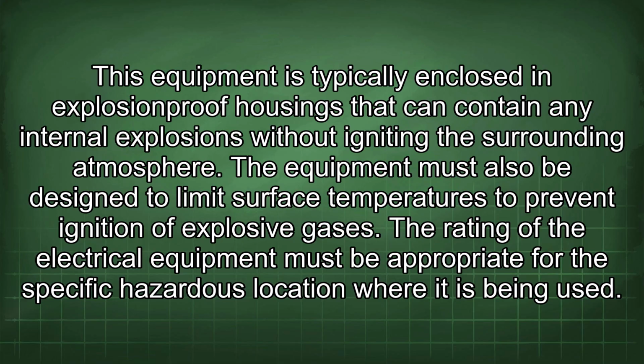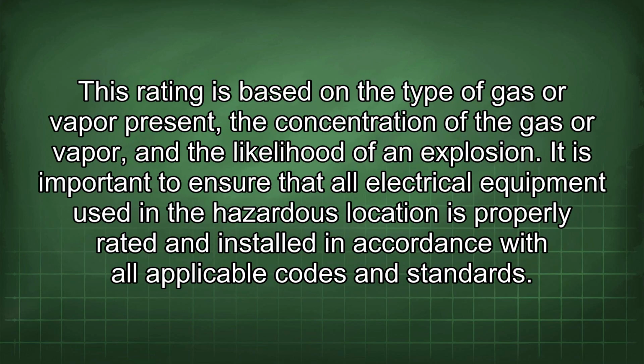The rating of the electrical equipment must be appropriate for the specific hazardous location where it is being used. This rating is based on the type of gas or vapor present, the concentration of the gas or vapor, and the likelihood of an explosion. It is important to ensure that all electrical equipment used in the hazardous location is properly rated and installed in accordance with all applicable codes and standards.